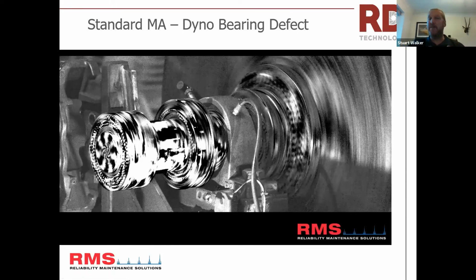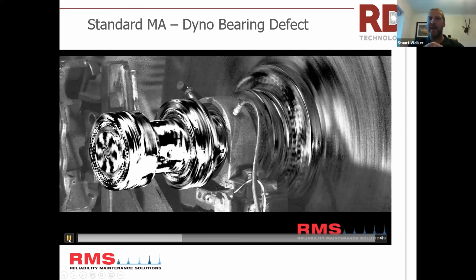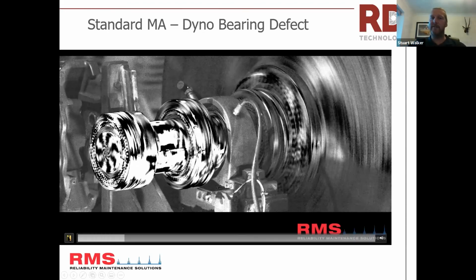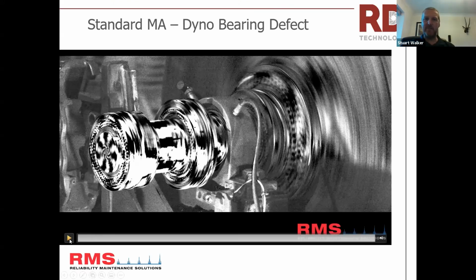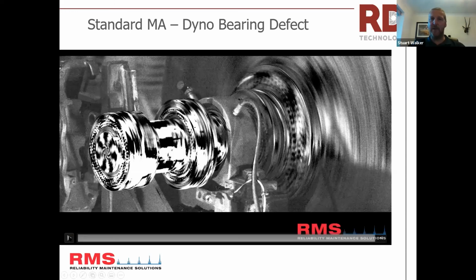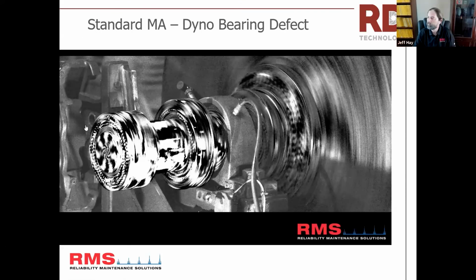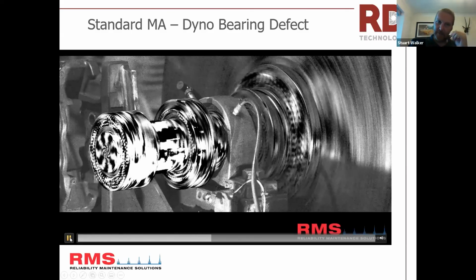I think it's related to the problem on this machine where they're having bearing problems, and I think the distortion of the bearing is causing the vibration at the outer race ball pass frequency. That's why it's the first harmonic. Now, it may be that there's some wear in there, but it's really even without any potholes impacting. So we're going to inspect the bearing and have a look, but I've no doubt it's to do with basically a weak bearing design on a real heavy flywheel doing 2000 RPM, just not up to these bearings, I think. But to see it is, that's crazy stuff.